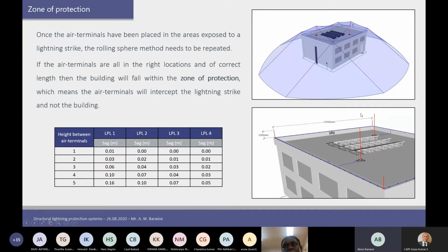Take the corners. So we have these, you see the 1 meter finials on the corners, right? Because the standard guided us. Take the corners, exposed edges and points, and place a certain height, pick a height, 1 meter, 2 meters, and then use the sag concept. So the sag concept is if you take the rolling sphere between, for example, this point here and that point there on the right of the building, if you had the rolling sphere in between these, the sag is the depth of that sphere itself from the top point to the bottom.